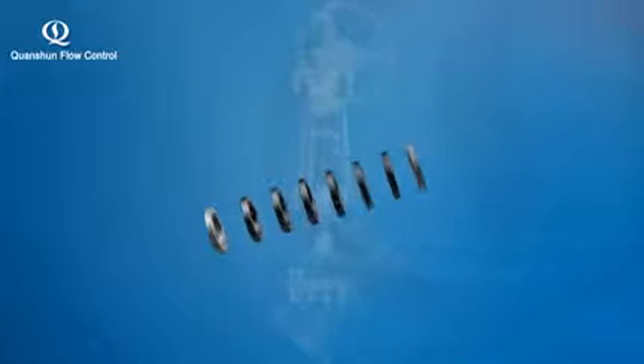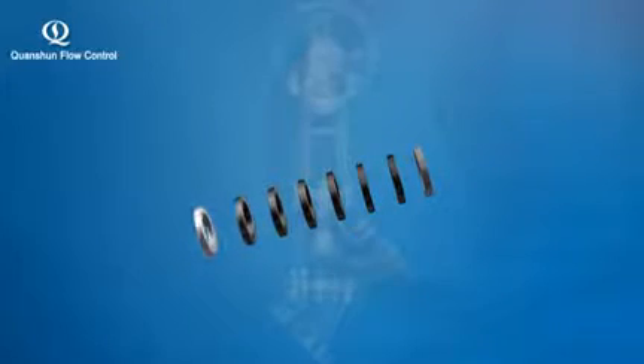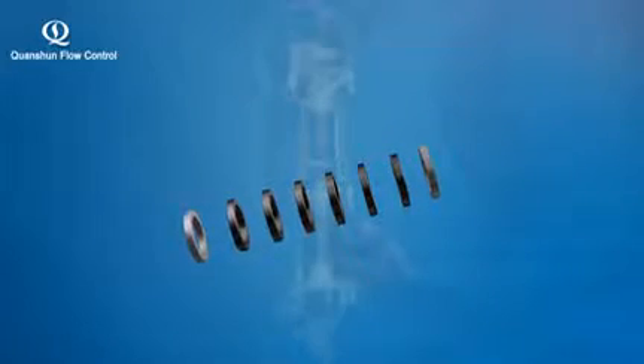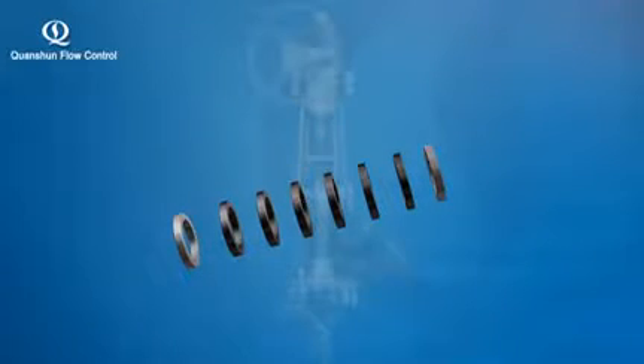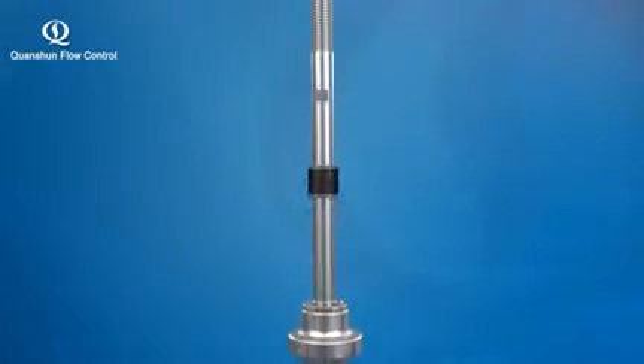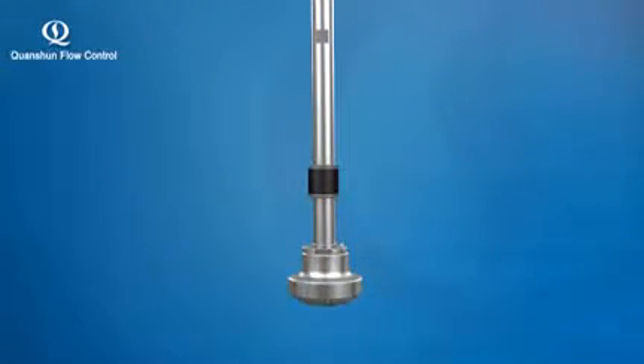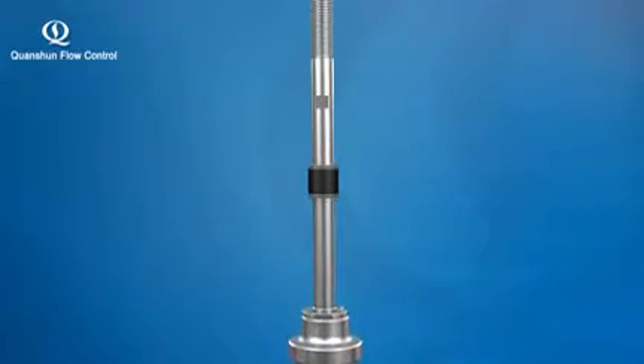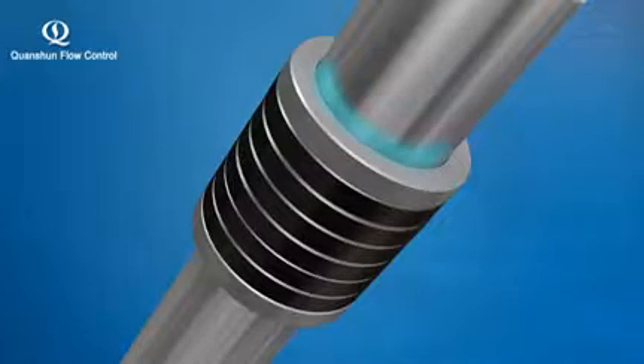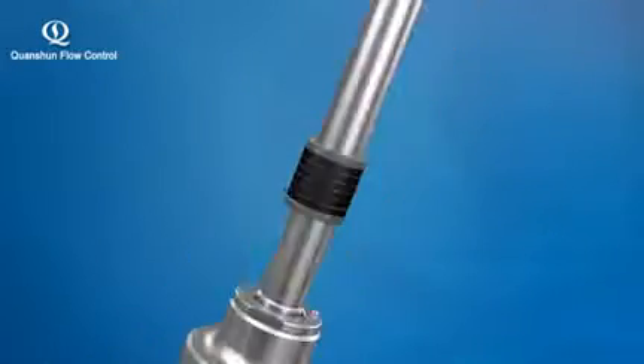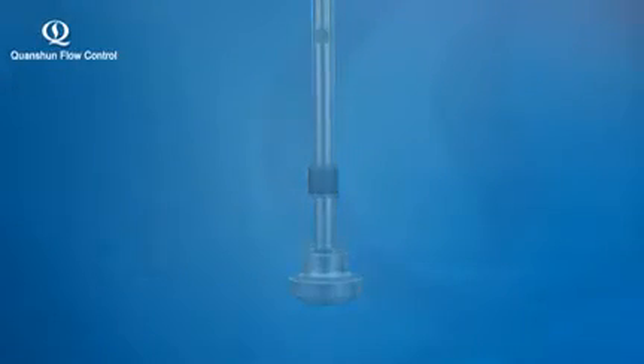6. Stem packing. With braided graphite wrapping the upper and lower positions respectively in 2 round turns and flexible graphite formed in between. This design guarantees the sealing strength of both the packing and the stem and effectively gets rid of the graphite powder attached to the stem during stem motion.